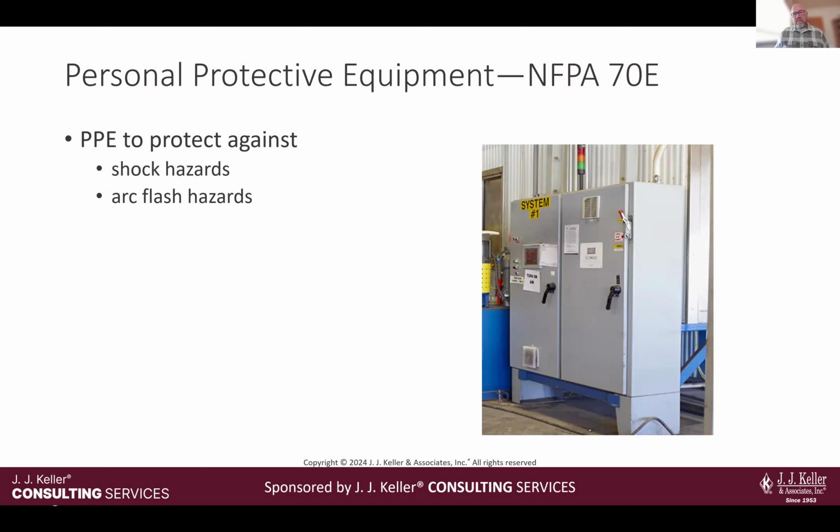If you are in a plant that has arc flash labels on it, you'll see that 18-inch working distance. The idea is we calculate 1.5 feet away from where that point of exposure would be, because that's where our face is. And the number on the arc flash label then gives us an indicator of what kind of gear we need to wear to prevent ourselves from some sort of thermal burn. It doesn't prevent the thermal burn, but the math is built on the premise that we want a 50-50 chance of people not getting a second-degree burn or worse. That's the idea. So if those odds are not good enough for you, then we need to maybe take a different approach.